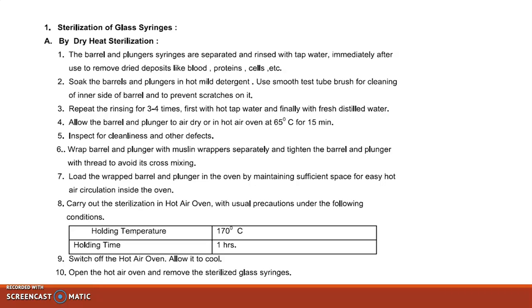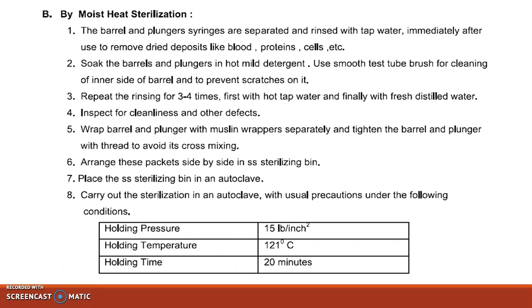circulation inside the oven. Carry out sterilization in the hot air oven with the usual precautions under the following conditions. The conditions we are going to maintain are holding temperature 170 degrees Celsius, holding time 1 hour. After achieving this condition, switch off the hot air oven, allow it to cool. Open the hot air oven and remove the sterilized glass syringes.